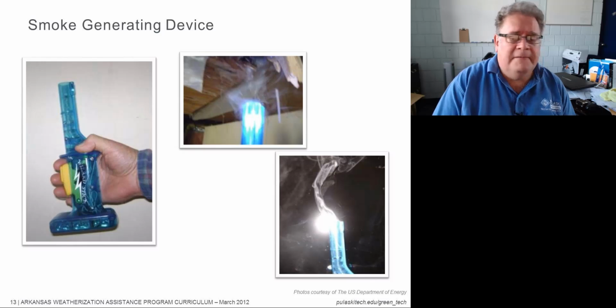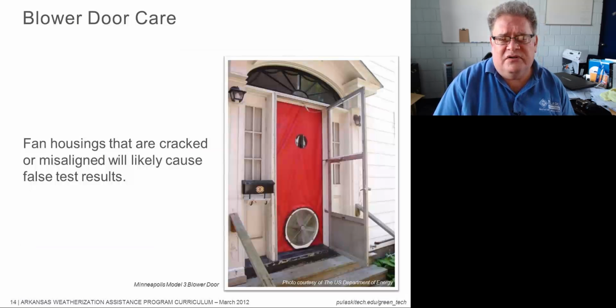All right, so your blower door, you need to check your fan housing on it, make sure that they are not cracked or bent. I have seen them bent. The fan housing is calibrated, meaning that it is designed to a specific shape and size. And if you've got a dent or a crack in it, then that changes that calibration. So make sure you don't have any problems.